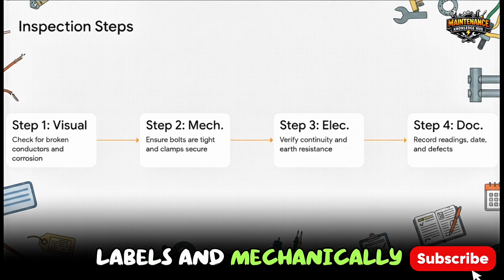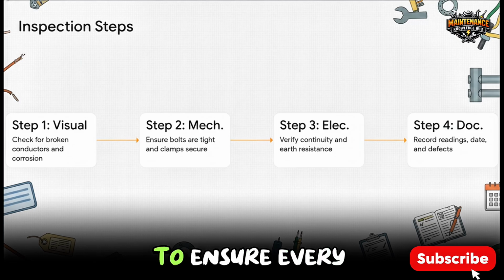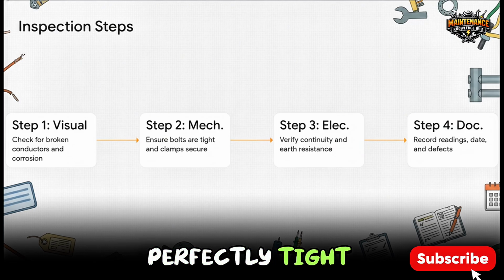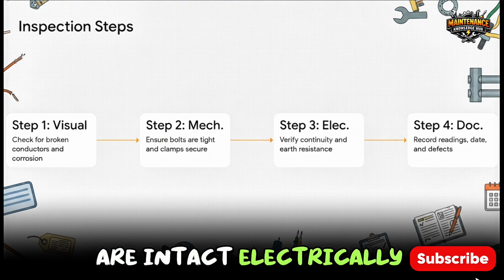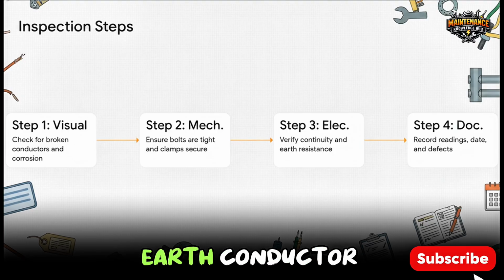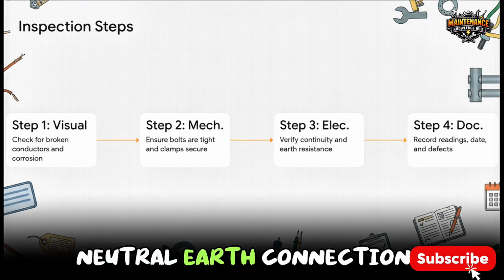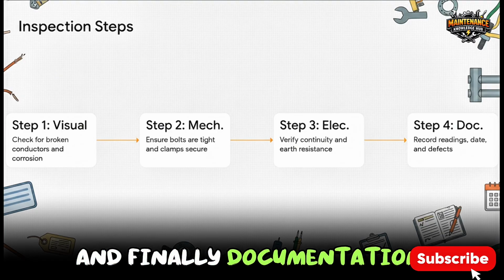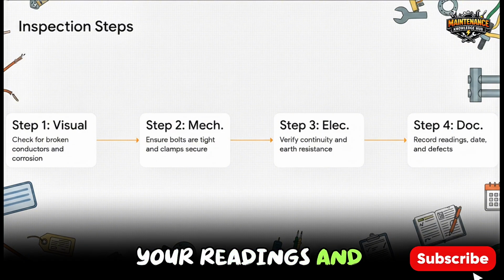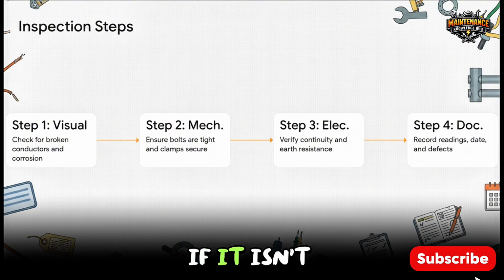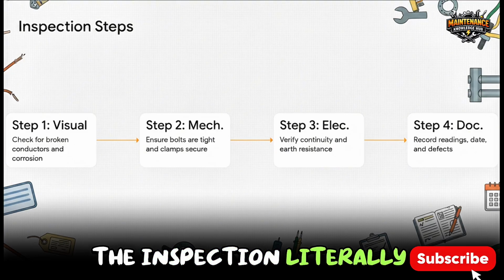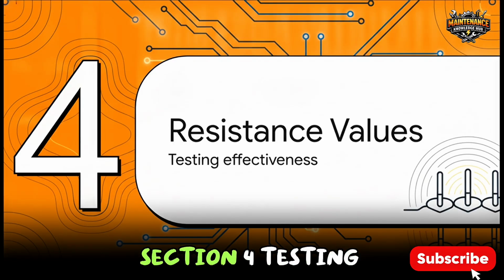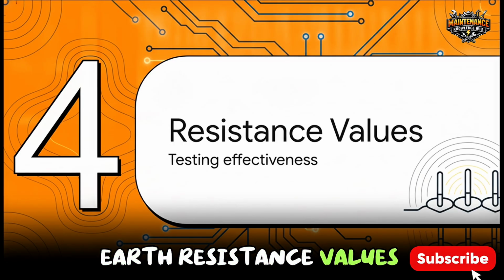Then, mechanically, you are getting right in there with a wrench to ensure every single bolt is perfectly tight and the welds are intact. Electrically, you're verifying the continuity of the earth conductor and checking those neutral earth connections. And finally, documentation. You got to record your readings and defects because legally speaking, if it isn't written down, the inspection literally didn't happen. All right, Section 4, testing earth resistance values.